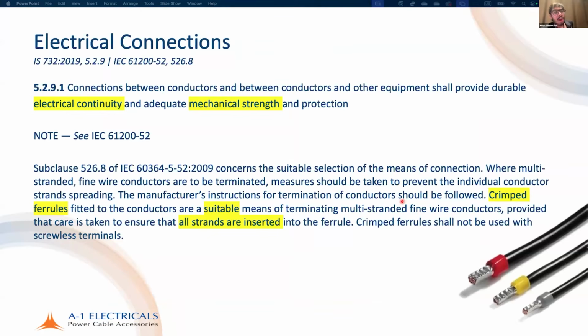Now, connections between conductors and between conductors and other equipment shall provide durable electrical continuity and adequate mechanical strength and protection. We already knew this. There's a note from IEC 61200-52, which says crimped ferrules fitted to the conductors are a suitable means of terminating multi-stranded fine wire conductors, provided that care is taken to ensure all strands are inserted into the ferrule. So, very important.